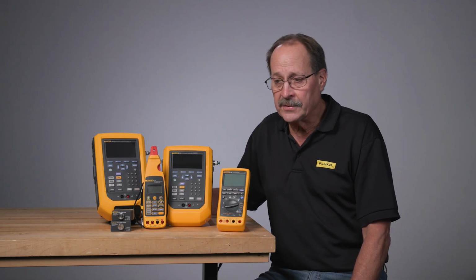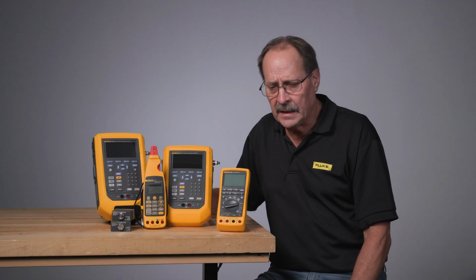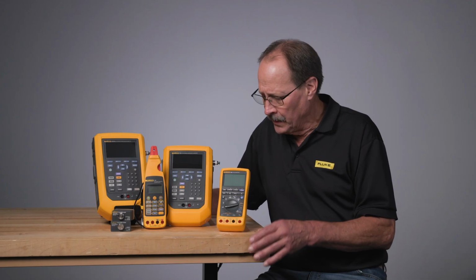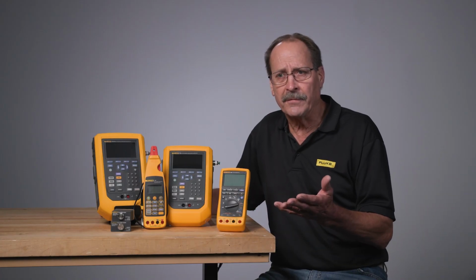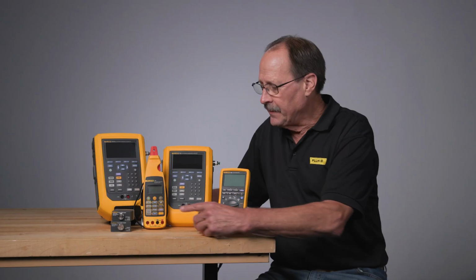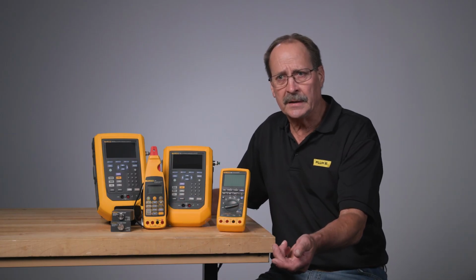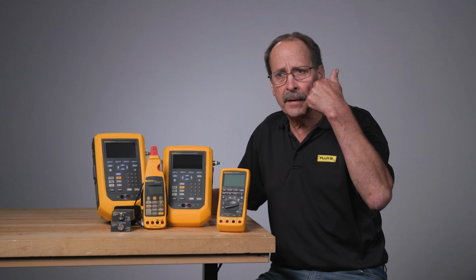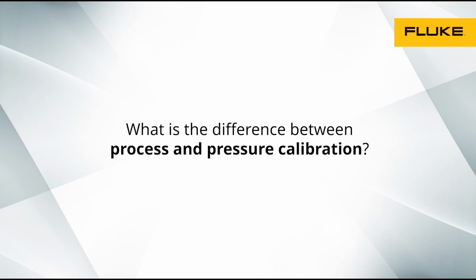And verifying those devices with a tool can be daunting. To measure a milliamp signal with a traditional multimeter, you have to break the loop open for making the measurement. Whereas if you have a process milliamp clamp meter, you can make that measurement without breaking the loop, talk to the operator in operations, and verify if the process is operating correctly.